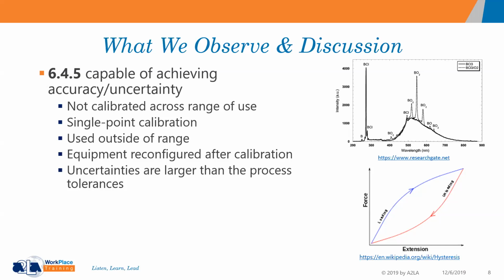The other point is we see that people are calibrating things at a single point, thinking that if they calibrate it there, it's good across the range. Well, if you look at the graph with the hysteresis diagram on the lower right-hand side, this is a force diagram that you would see, extension based on extensometer and displacement for mechanical deformation. If that point doesn't happen to lie on that hysteresis graph somewhere, you can see that you're introducing a significant amount of error in your measurements. So this is why we're seeing a lot of this. And a lot of people think, well, it's cheaper to get a single point, but is it really cheaper in the long run?